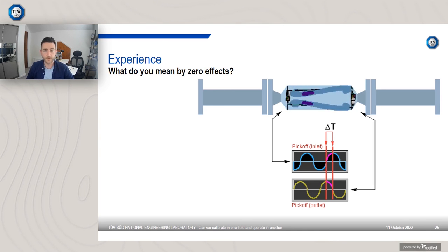I have a Coriolis schematic here, obviously exaggerated with respect to the twisting of the tubes, but I'm sure most folk will be aware of how Coriolis meters operate. Ultimately you have a driver in the centre that oscillates the tubes at its resonant frequency. If there's no fluid passing through, the two tubes oscillate in phase and there's no delta T, no phase shift. However, once you introduce some fluid through the Coriolis meter, there's a pick off at the inlet, a pick off at the outlet, and with increasing mass flow, you get a larger delta T. So it's more out of phase between the two sets of pick offs between inlet and outlet. That is directly proportional to your mass flow rate.